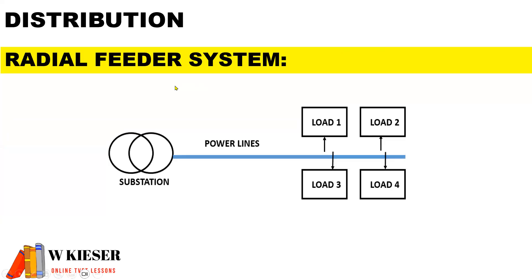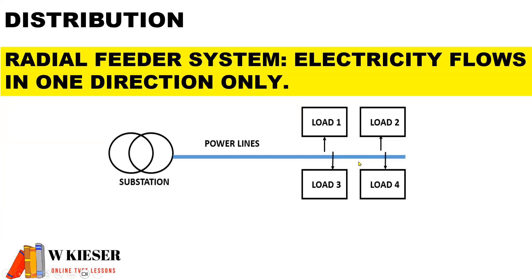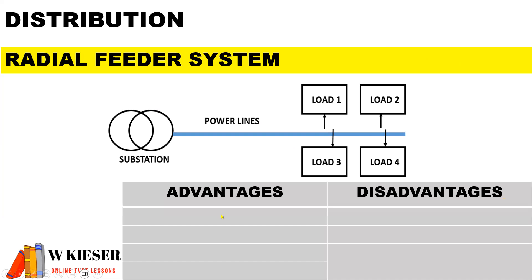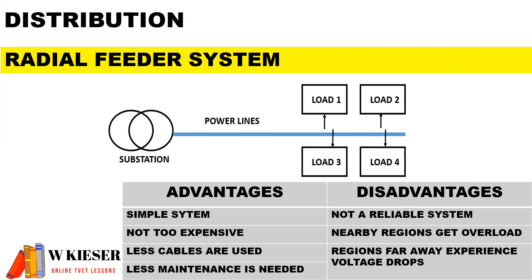For the radial feeder system, you'll notice that we have a single power line, and this allows electricity to flow only in one direction. In terms of the advantages, it is a simple system, not too expensive, less cables are used and less maintenance is required. However, for the disadvantages, it is not a reliable system. Nearby regions get overloaded and regions far away experience voltage drops.